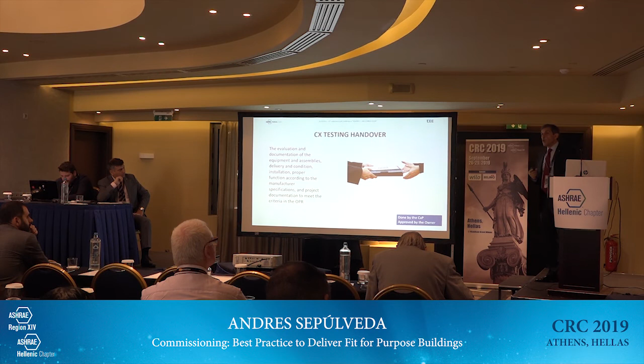At the final phase of the building life cycle, of course, complete the commissioning outstanding activities or issues, and conduct what we call the seasonal deferred testing, because the building was delivered in April and no summer load was available to make summer testing possible. Complete documentation, take any opportunity to further improve the building's performance, and prepare a solid ongoing commissioning plan.